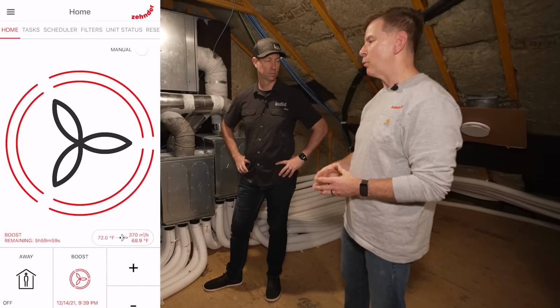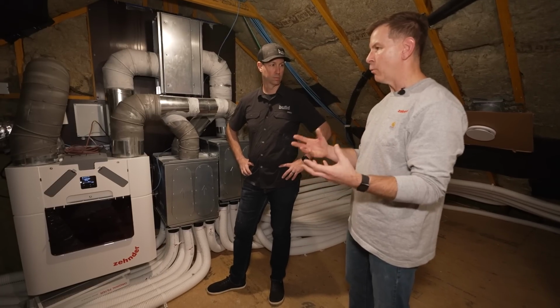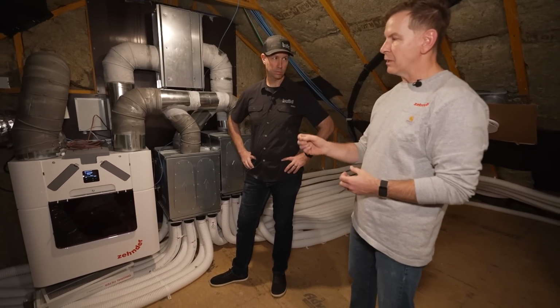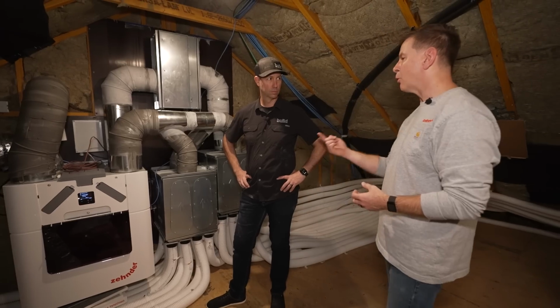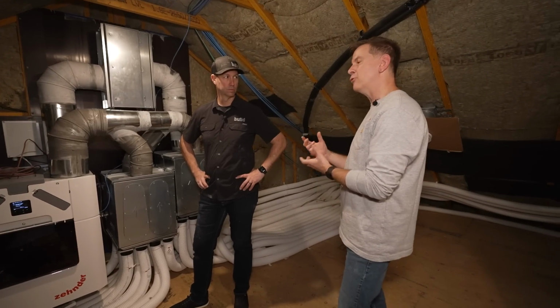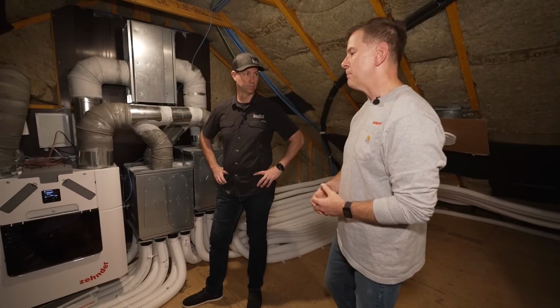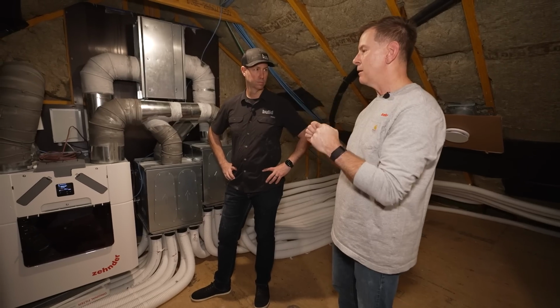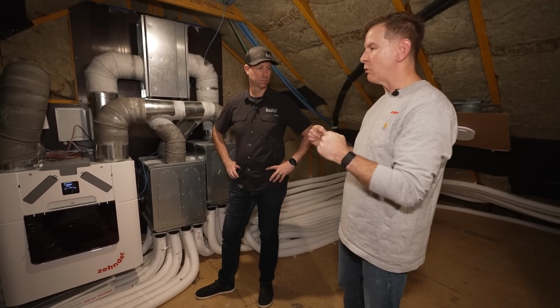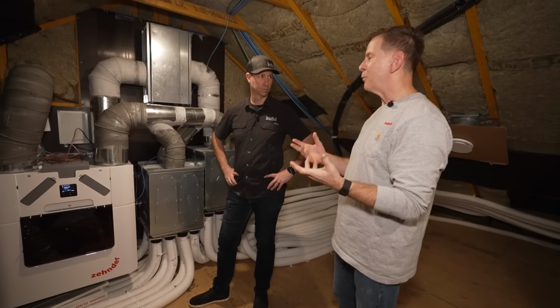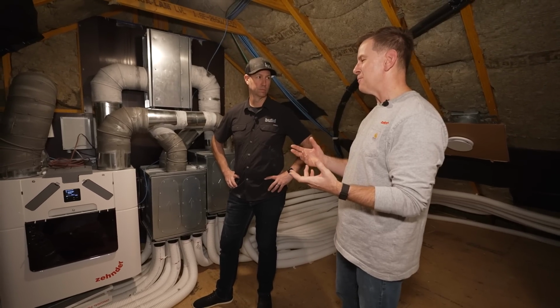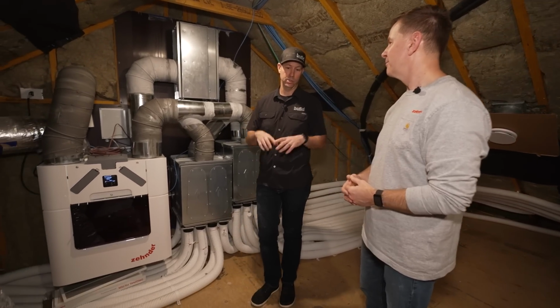Based on what you can get out of the system and what you want and what you designed it for, you'll get those settings. Then it's time to go around and check each individual diffuser, check the flow, see what you get. We'll record that once, then decide where to start tweaking, and once it's all tweaked, that system's ready to go.